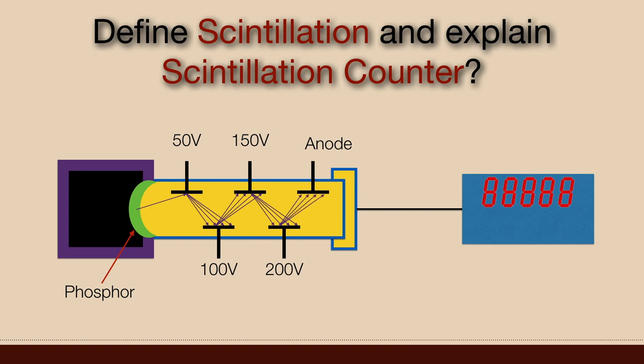Each incident electron on the surface of dynode is capable to eject four electrons. Thus, the electrons go on multiplying. Finally, all these accelerated and multiplied electrons are incident on photoanode which is fixed at the other end of the photomultiplier tube.